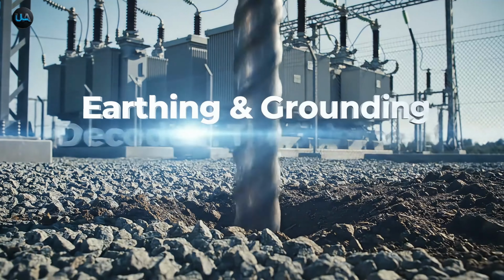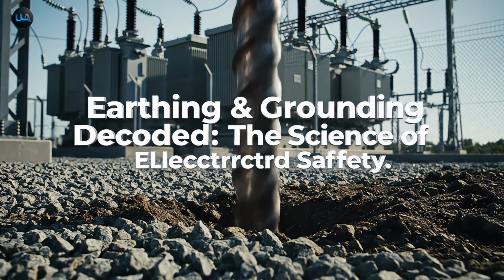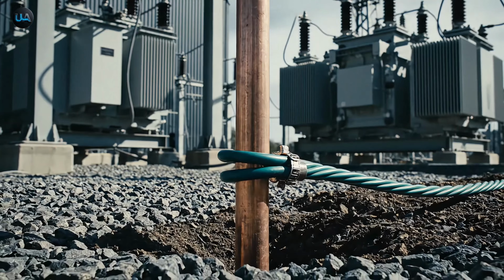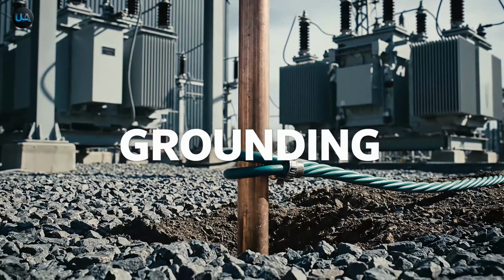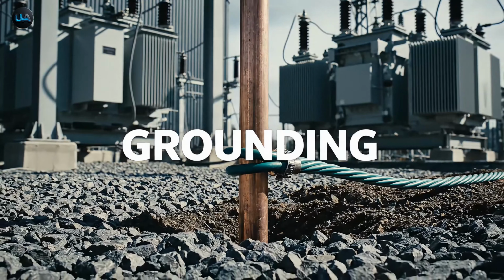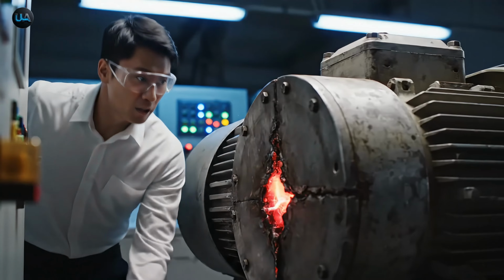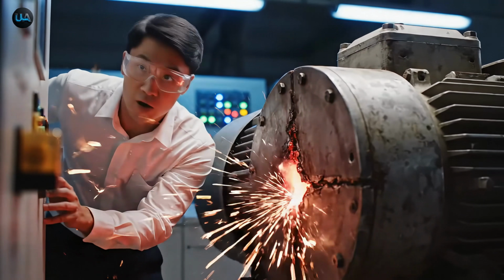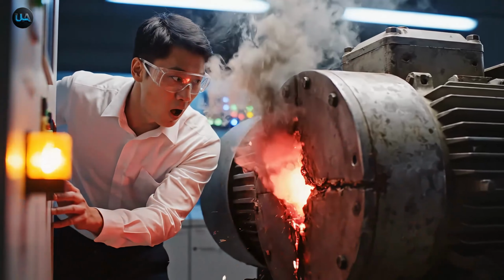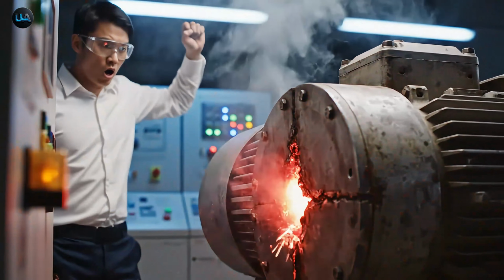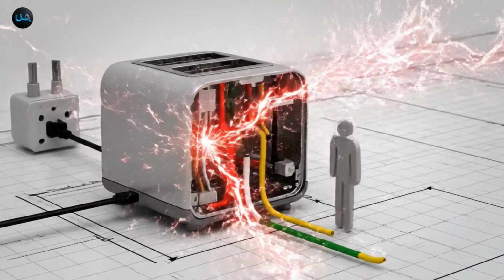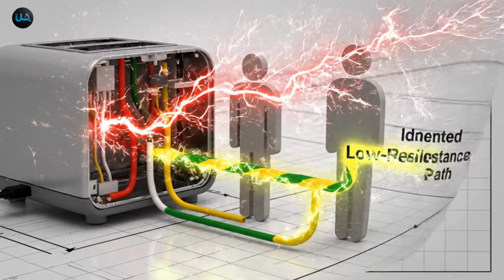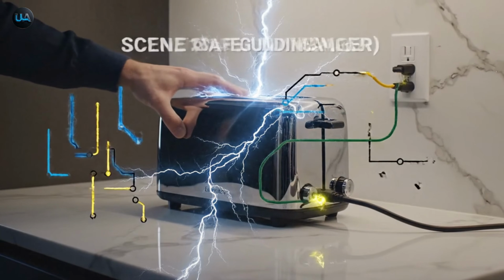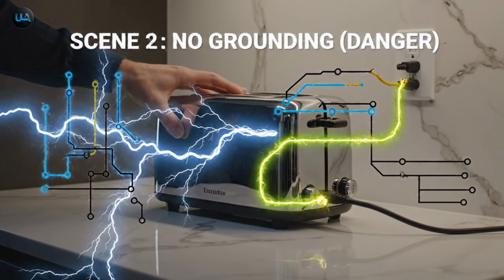It is the unseen guardian of every electrical system, a safety net buried beneath the earth. Earthing and grounding are the absolute foundation of electrical safety. The core challenge is the fault current, uncontrolled electricity caused by insulation failure or short circuits, which can electrocute people or destroy equipment. The primary goal of grounding is to provide an easy, low-resistance path for that fault current, diverting it away from humans and sensitive components.